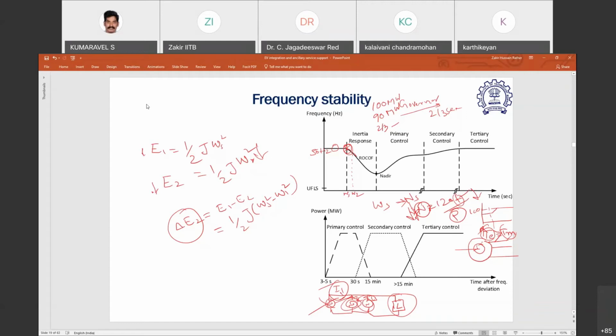As the machine speed goes down, the grid frequency falls down. So this inherent release of energy by the machines, at the cost of the decrease in their speed, is what precisely balances the generation and load before this governor control kicks in. In the initial 2-3 seconds from the onset of the disturbance, it is this rotational energy which is released by these rotating machines to the grid and balances generation and load. As I mentioned earlier, if that does not happen, the grid will collapse ideally.